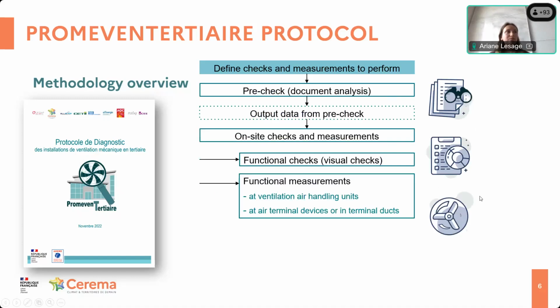Then there are functional measurements at ventilation air handling units and at air terminal devices or in terminal ducts. So the visual inspection includes, for instance, cleanliness and correct operation of air terminal devices, proper positioning of air inlets and outlets to avoid short-circuiting airflow, or quality of duct connections on visible parts only, because these checks are non-destructive. And it is important to mention that.